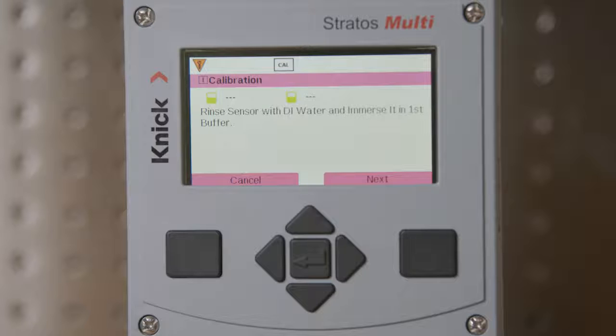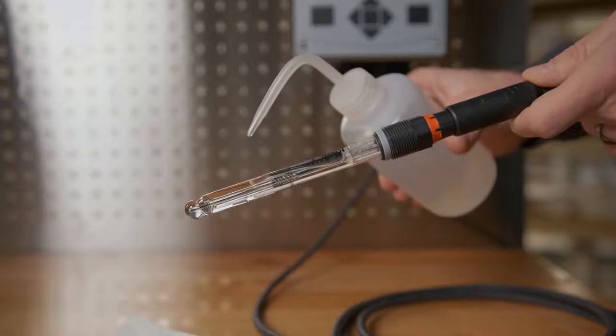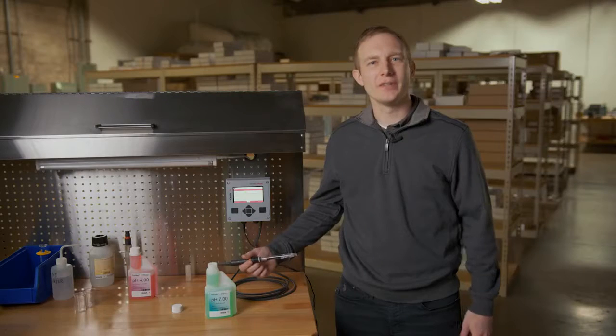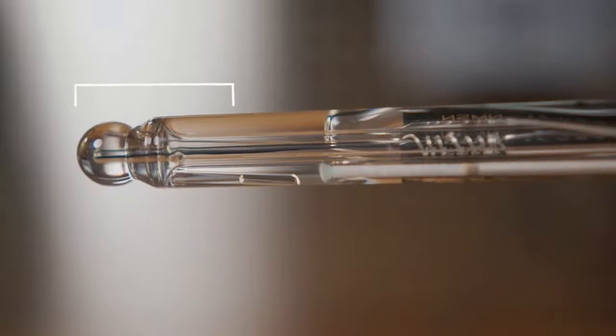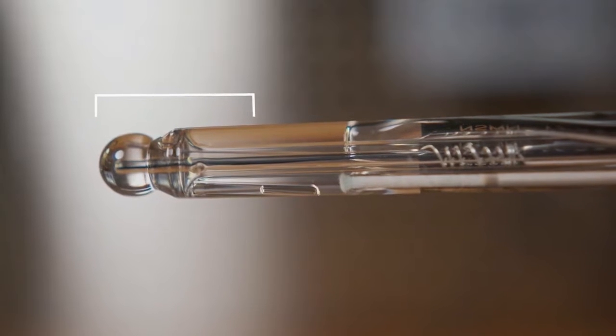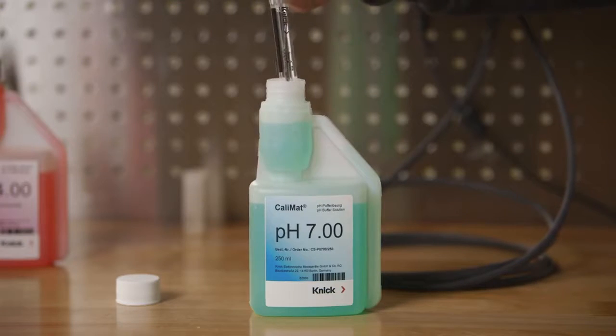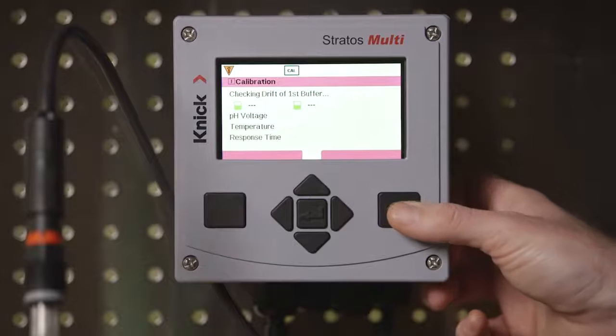Here, we are prompted to rinse our sensor with DI water and place it in our first buffer solution. We will do so and place the sensor into the buffer 7. We want to ensure that the entire pH measuring bulb, along with the sensor's junction, are immersed in the buffer. We will stir lightly and then press the Next button.